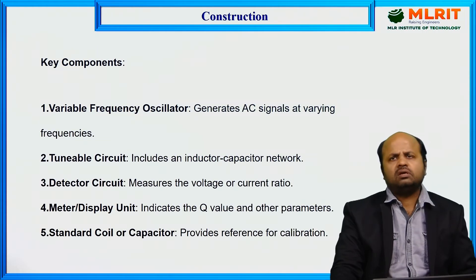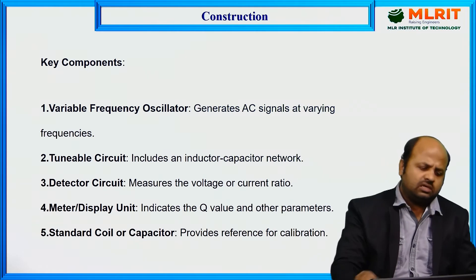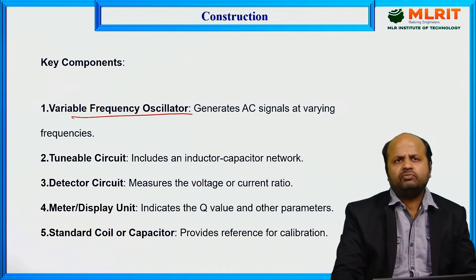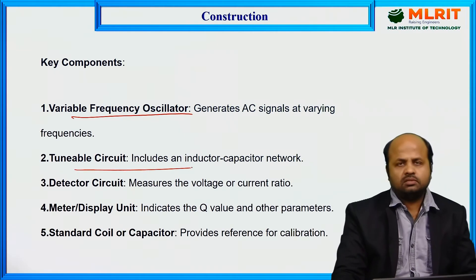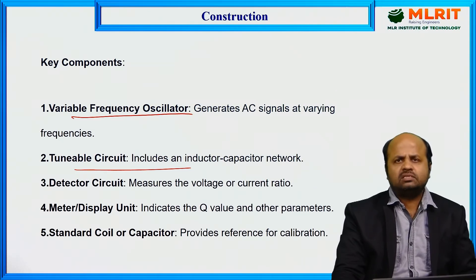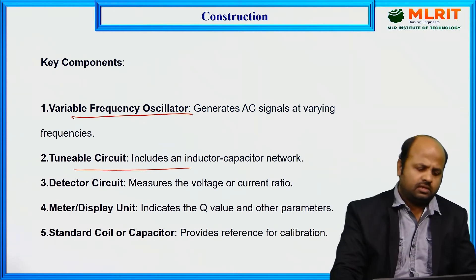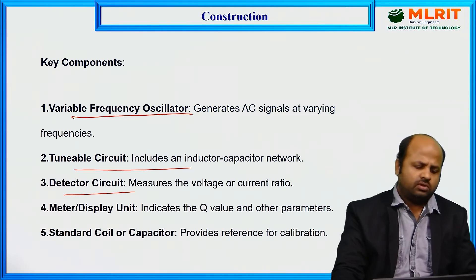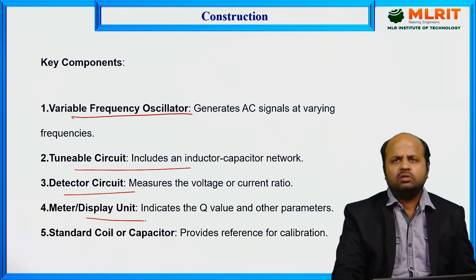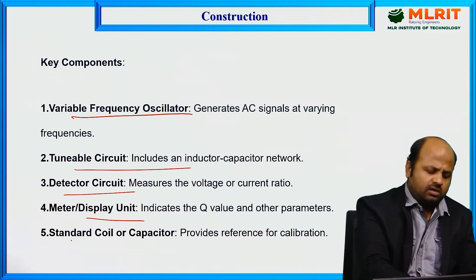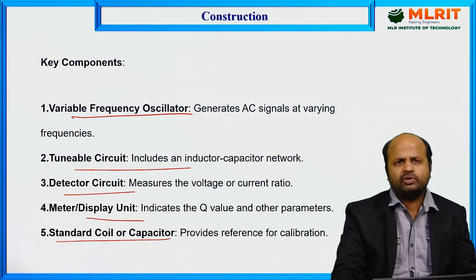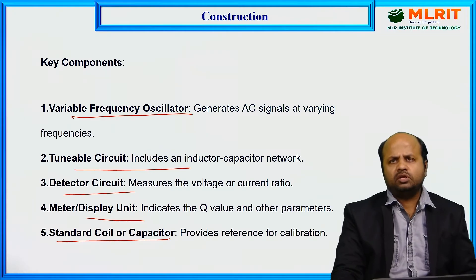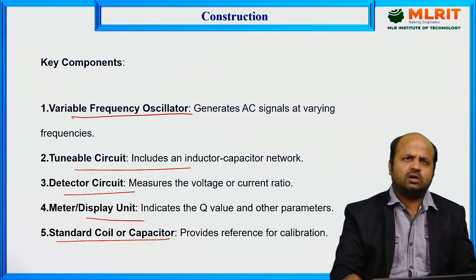These are some of the key components of a Q-meter. A Q-meter generally consists of a frequency oscillator, which generates an AC signal of variable frequencies; a tunable circuit, which is essentially an LC circuit used to select a particular frequency; a detector circuit, which measures the voltage or current ratio; a display unit where Q-meter values are displayed; and a standard coil or capacitor, which provides a reference for the calibration of the Q-meter.